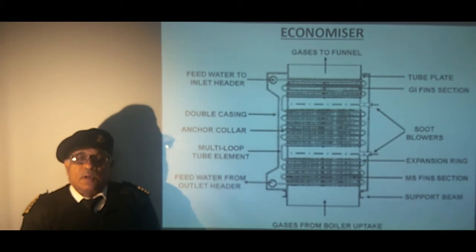It consists of solid forged mild steel inlet and outlet headers to which multi loop tube elements are attached by expansion and bell mouthing or welding through stub tubes. Solid drawn mild steel tubes with MS fins are used for temperature above 138 degree centigrade whereas GI fins are used below this temperature in order to protect plain tube from corrosive attack. Tubes are supported by tube plates and are equipped with soot blowing arrangement to maintain clean tube surface for high efficiency and to prevent the uptake fire.